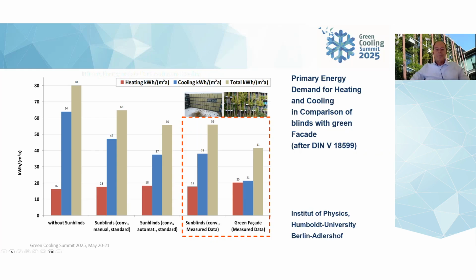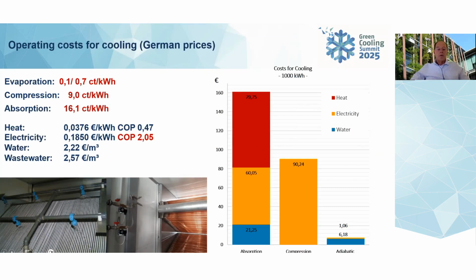The next slide, please. In this building, we are using rainwater as well for evaporative cooling in air conditioners. And you evaporate rainwater into the exhaust air, not to get an increase in humidity inside. And if you compare, because we have in this building 3 parts of cooling, we have absorption chillers of York, compression by Trane, and adiabatic cooling in air conditioners. Adiabatic cooling with rainwater costs 0.1 cent per kilowatt hour. If you would use tap water, it would be 0.7. Compression is 9 cents per kilowatt hours, and absorption 16.1 cent per kilowatt hours for German prices.